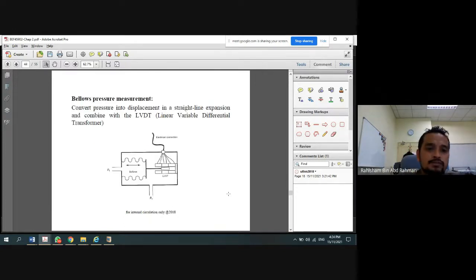Okay, bellows pressure measurements. Again, these are the bellows. Like I said just now, as I mentioned before, we have a pressure that goes into the bellows, and this bellows, if you can imagine, the bellows is something like the plastic things that you can compress or outstretch. So it will move depending on the pressure. So the movement of these bellows will move the LVDT. This is the sensor, LVDT. This one is connected to the display device. So based on this one, also we can measure the difference.